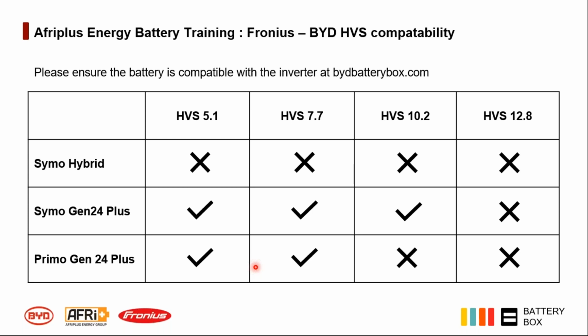So your HVS can do that. If you need 10 kilowatts of backup, you can use 10 kilowatt hours of HVS battery, and you can parallel two towers. So your HVS can supply your small scale and your medium scale installations. Your HVM can only supply your medium scale, and it can't supply your small scale very easily. So that's the reason there's only the HVS available in the Southern African region at the moment.